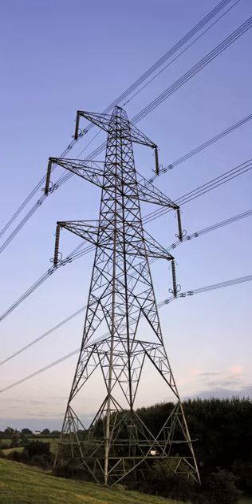For single-pole HVDC transmission with ground return, towers with only one conductor can be used. In many cases, however, the towers are designed for later conversion to a two-pole system. In these cases, often conductors on both sides of the tower are installed for mechanical reasons.